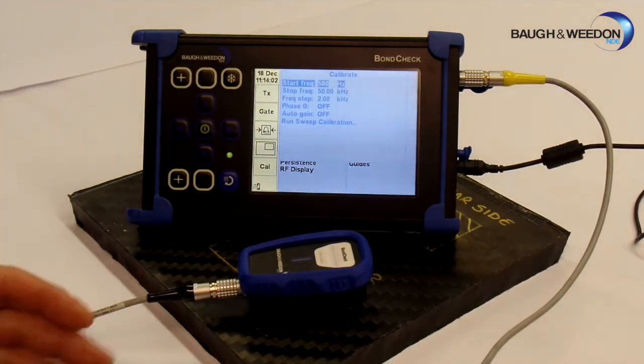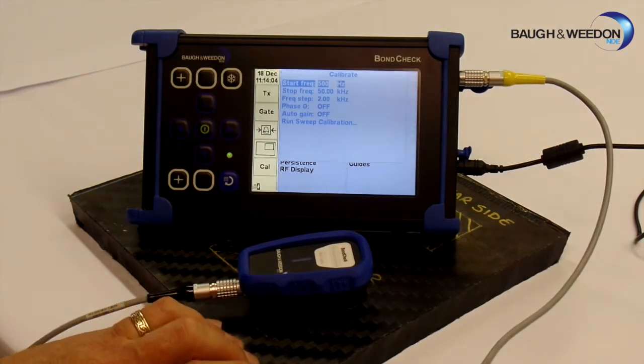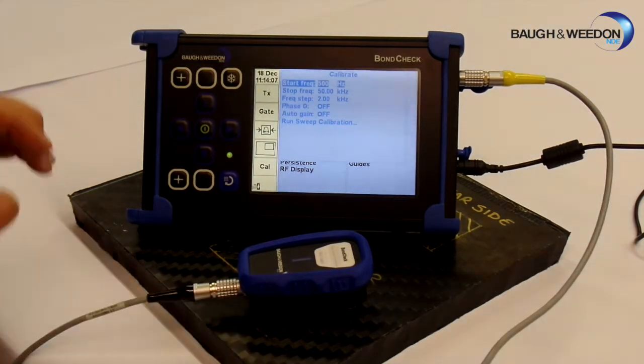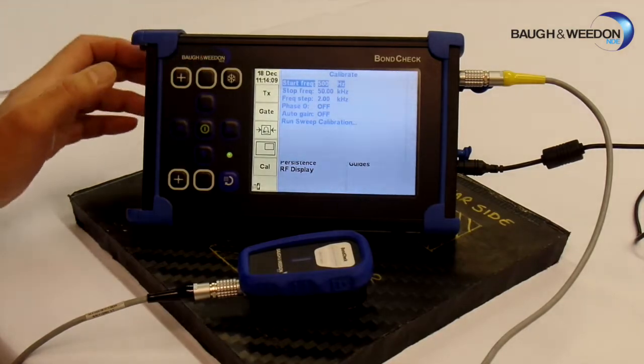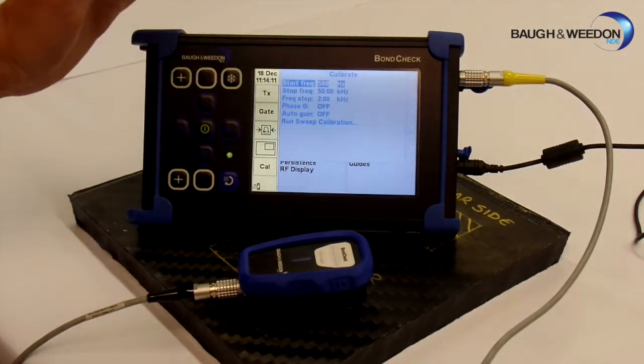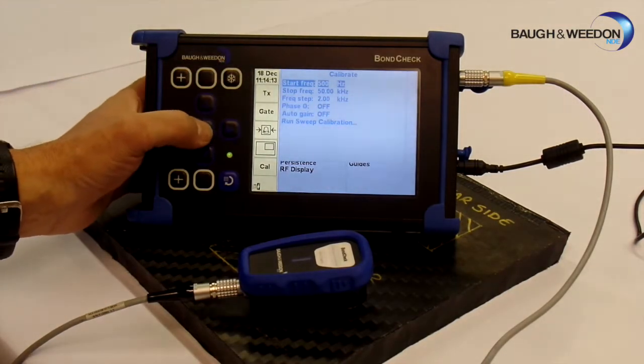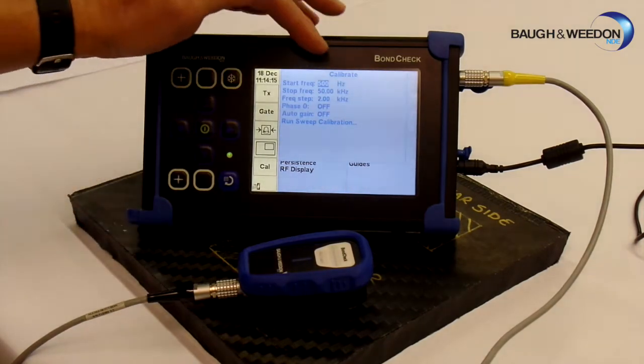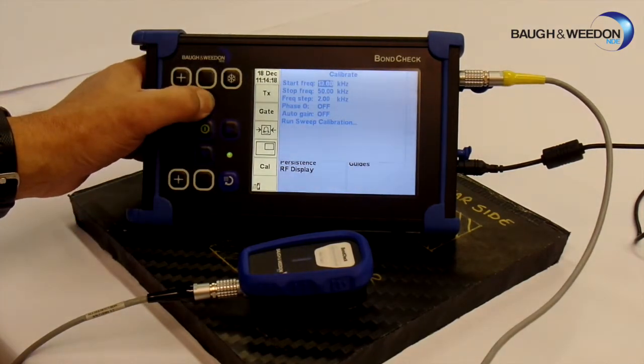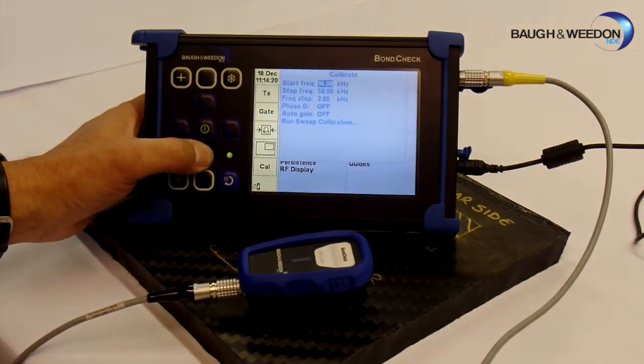But in this instance, as I said, we are going to carry out a calibration on this piece as if we had not done it before. So we are going to leave it open to the maximum. But to actually adjust the frequencies, what we would do is press the green button, it is now highlighted the 500. We can't take it down anymore, but we could take it up, we could take it back down again.